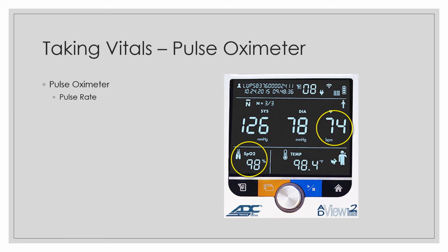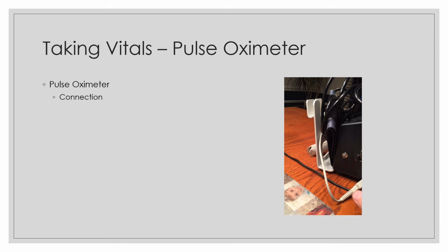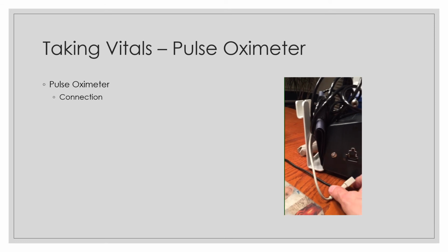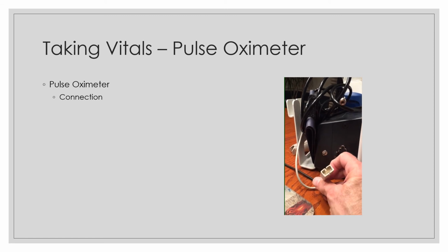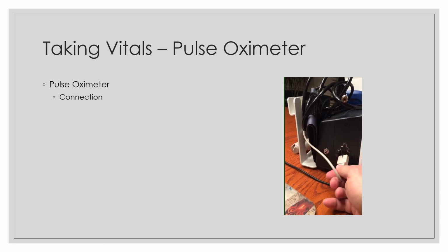The pulse ox, or oxygen saturation percent, will appear in the lower left of the display. The sensor will also calculate the patient's heart rate, which will display on the right side of the middle row, in beats per minute. If the pulse oximeter cable is not connected to the unit, connect it by matching the D-shell connector receptacle on the left side of the ADView2.